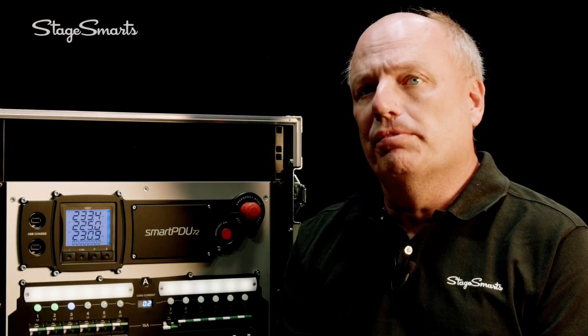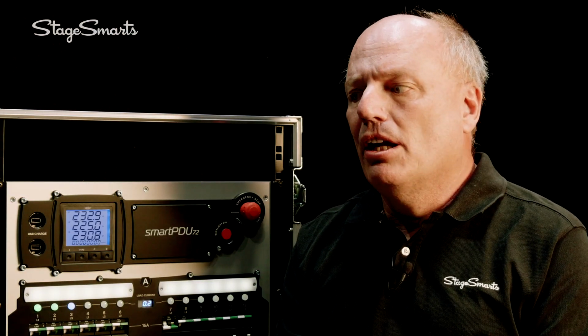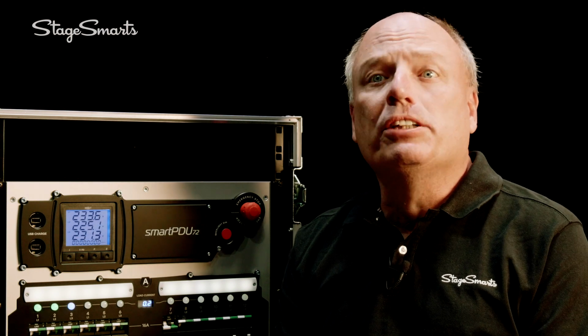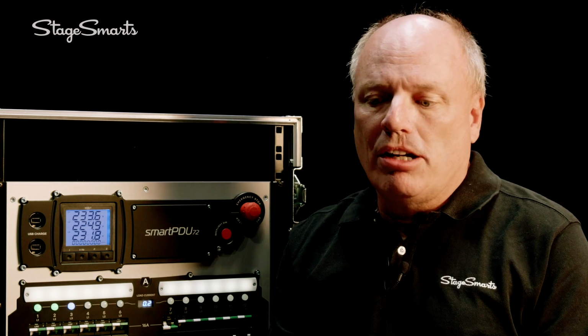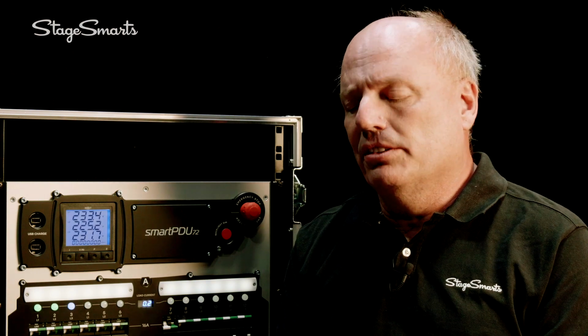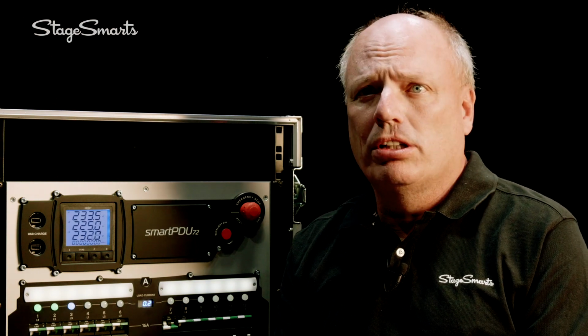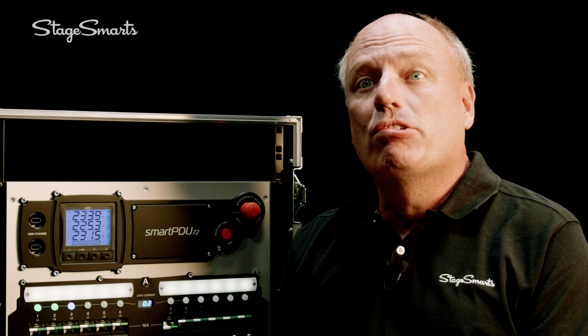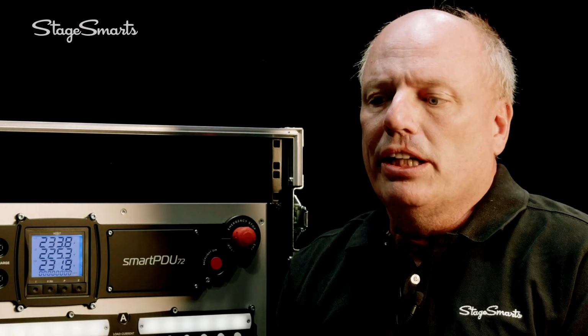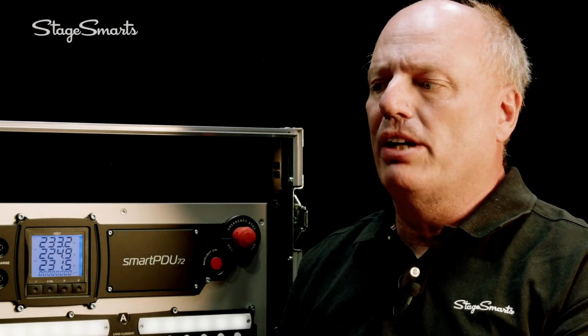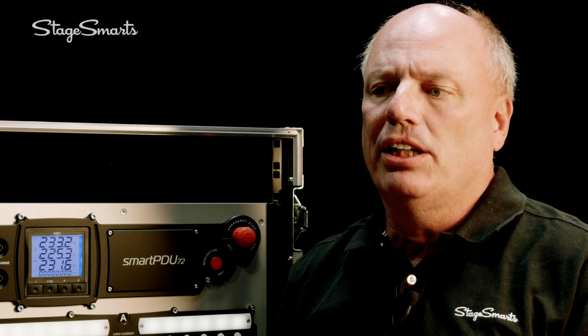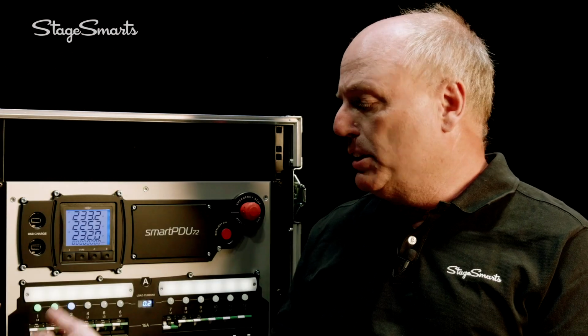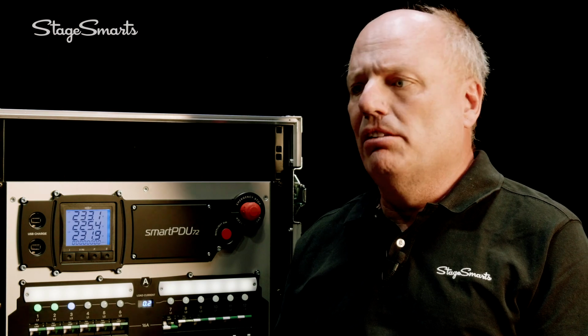Early adoption from the industry has been companies renting out large LED video screens. For example, right now we have 2 of these 72-way racks out on the big worldwide Roger Waters tour, powering 1,400 LED panels. Previously, rental companies would have to use multiple racks because the leakage currents added up and started tripping the breakers. These breakers are much more resilient, so they can deal with those tough loads.